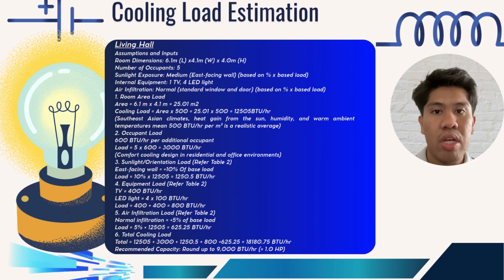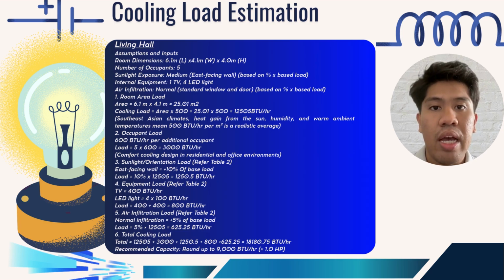Next, we go to the equipment loads. There are internal heat sources in the room, including a TV and 4 LED. The estimated heat gain for the TV is 400 BTU per hour, and for LED, 4 multiply 100 BTU per hour. The total equipment load is 800 BTU per hour. And lastly, air infiltration load. Normal air infiltration adds an additional 5% of the base load, so the total air infiltration load is 625.25 BTU per hour.